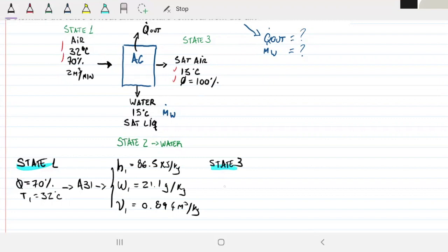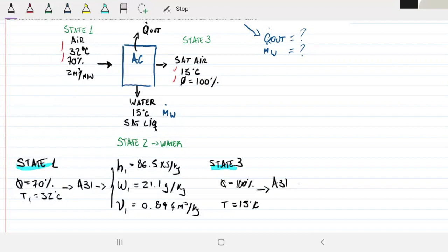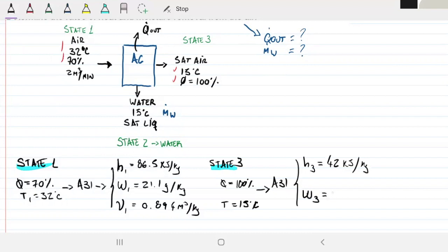For state three: I know the relative humidity is 100% and the temperature is 15°C. From the calculator, the enthalpy h₃ = 42 kJ/kg dry air and ω₃ = 10.7 grams of water per kilogram of dry air. I don't need the specific volume for state three since I'll use state one's specific volume to calculate the mass flow rate.